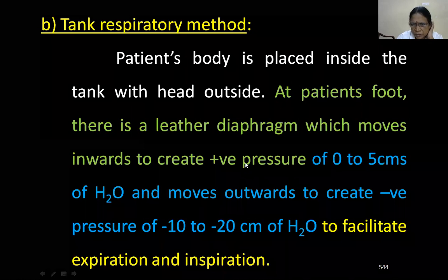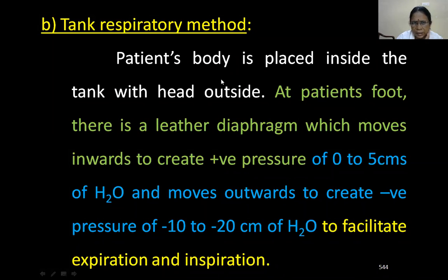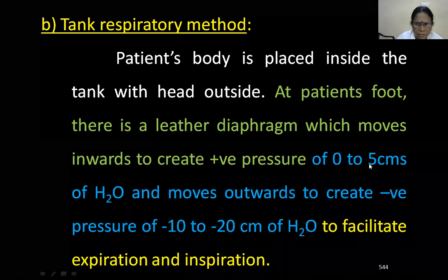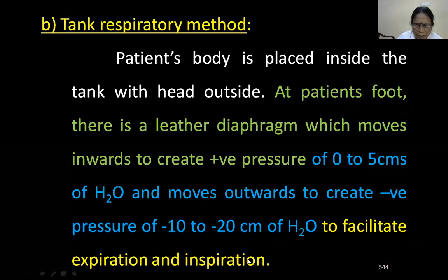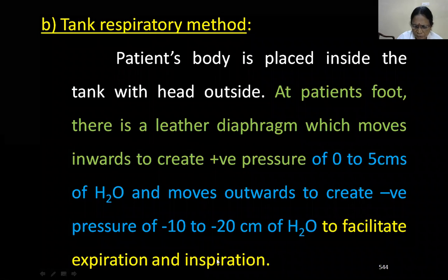The patient's body is placed inside a tank, with the head outside and the diaphragm at the foot end. The inward movement causes a positive pressure of 0 to 5, and the outward movement causes minus 10 to minus 20. Negative pressures cause inspiration, positive pressures cause expiration.